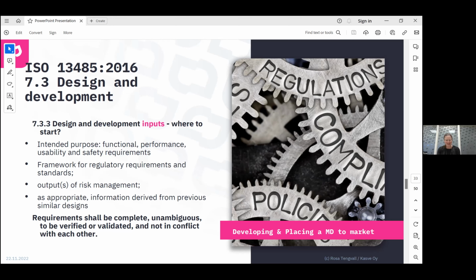Design inputting, or the requirement setting, shall be complete and not in conflict with each other. The important thing is that each requirement must be verified or validated, so you need to state the requirement so that you can actually test it, in such a specific manner that you can have the test derived from the requirement, and the validation also.